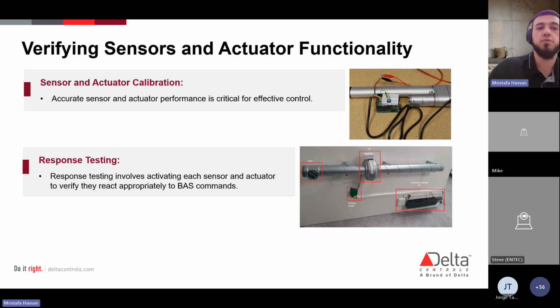So when it comes to commissioning, right, you want to verify sensor and actuator functioning. You're making sure that all this stuff is calibrated. So accurate sensor and actuator performance, right, is critical for effective control. Calibration is going to ensure that your sensors will actually provide reliable data within the specific tolerances that you specify, right? And that the actuators respond precisely to the controller commands. And that's going to minimize errors in system behavior.